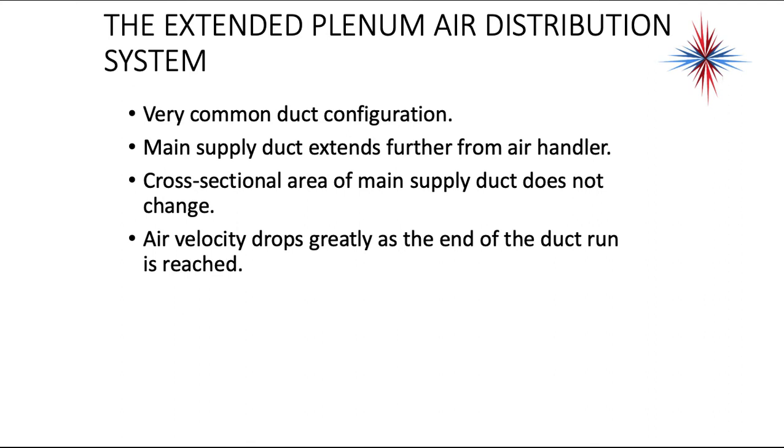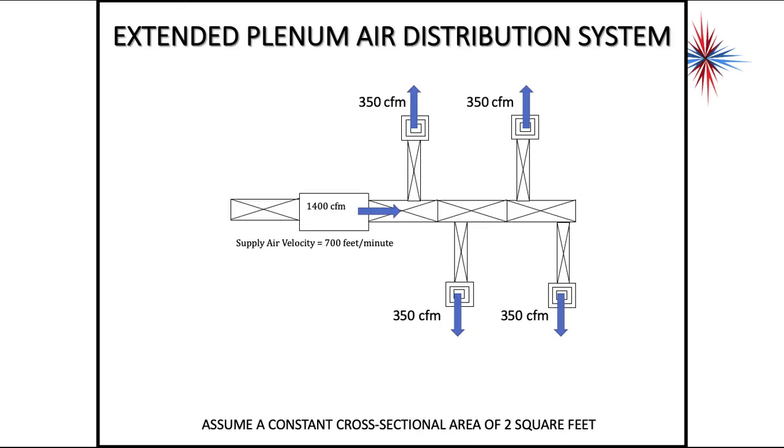The extended plenum air distribution system, which is what I just showed you, is a very common duct configuration. The main supply duct extends out further from the air handler. The cross-sectional area of the main supply duct does not change, so it's one size. So if at the air handler, it's 24 by 36, it is going to be that size all the way down through the end of the duct. The air velocity drops greatly as the end of the duct run is reached, because there's nothing going on to maintain velocity.